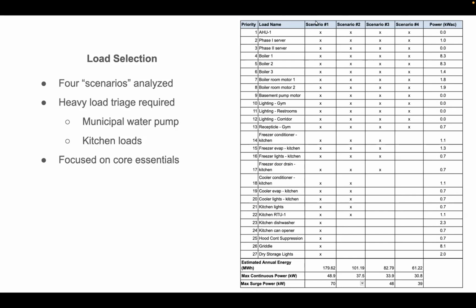These scenarios model 4 different cases. Scenario 1 includes all the loads on the list. Scenario 2 cuts off some unnecessary kitchen items and has everything else. Scenario 3 cuts off additional unnecessary kitchen items, leaving basic refrigeration, lighting and receptacles, and heating and cooling in certain areas of the building. Scenario 4 cuts out even the refrigeration — so you'd let your food spoil, but you still get heating, cooling, lights, and receptacles. There was a lot of triage involved.